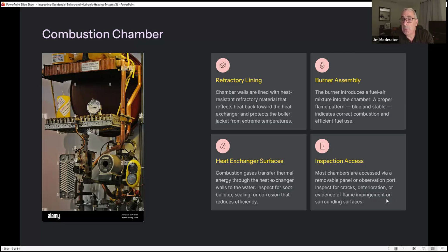The burner introduces a fuel-air mixture into the chamber. A proper flame pattern, blue and stable, indicates correct combustion and efficient fuel use. Heat exchanger surfaces. Combustion gases transfer thermal energy through the heat exchanger walls to the water. Inspect for soot buildup, scaling, or corrosion that reduces efficiency. Inspection access. Most chambers are accessed via removable panel or observation port. Inspect for cracks, deterioration, or evidence of flame impingement on surrounding surfaces.